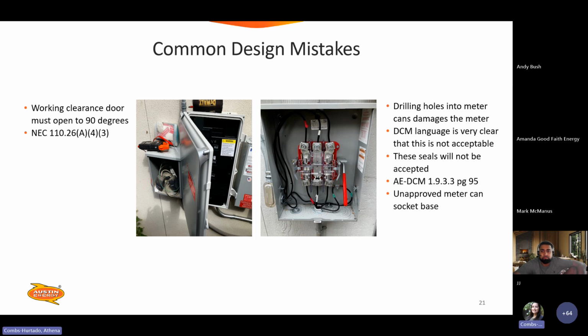All right, some common design mistakes are working clearance. The door must open to 90 degrees, so make sure that you double check and open it all the way. Also, drilling holes into the meter can damage the meter. Per our DCM, the language is pretty clear that we are not able to accept these, and page 95 shows that information.